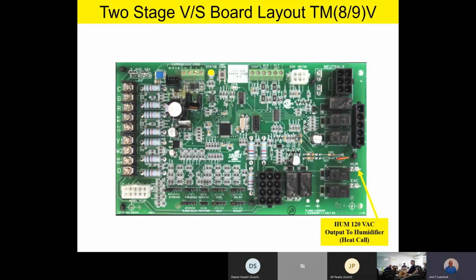As we move down the board, you're going to notice we have a 120 volt output for a humidifier. Anytime you have a heating call generated on the board from the thermostat, you'll have an output on that HUM terminal. And that HUM terminal, by the way, is 120 volt. So if you want to power a humidifier right off the board, you can do that. This is something I really like about our Champion product: we give you accessories on the control board itself to hook up a humidifier, an electronic air cleaner and stuff like that, because a lot of manufacturers have you use a separate relay pack or a separate power source or whatever. So this is kind of cool.